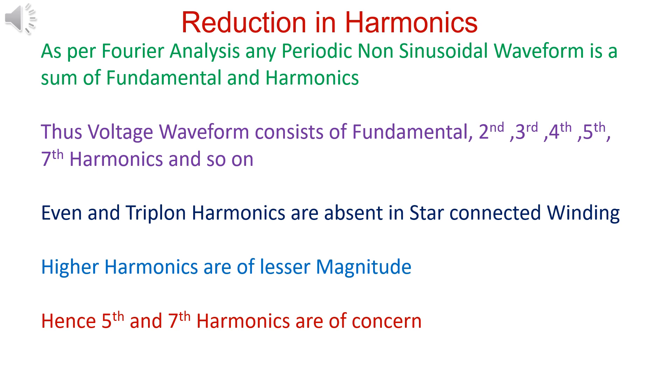As per Fourier analysis, any distorted periodic waveform consists of fundamental and harmonics. In star connected stator winding, even and triplen harmonics are absent. Higher harmonics are of lesser magnitude. Hence, fifth and seventh harmonics are of concern.